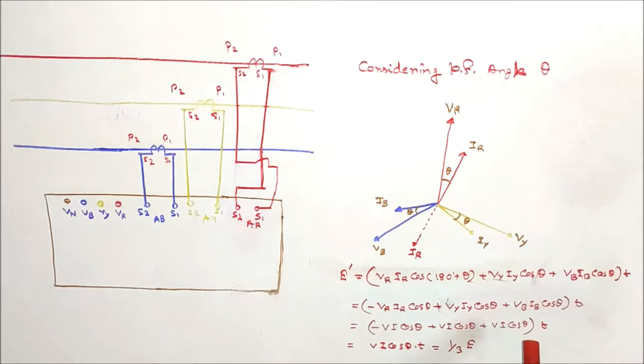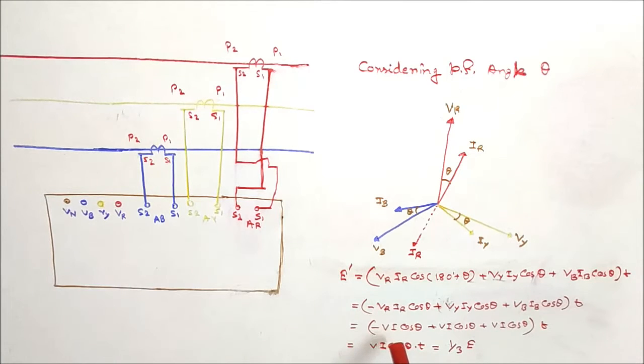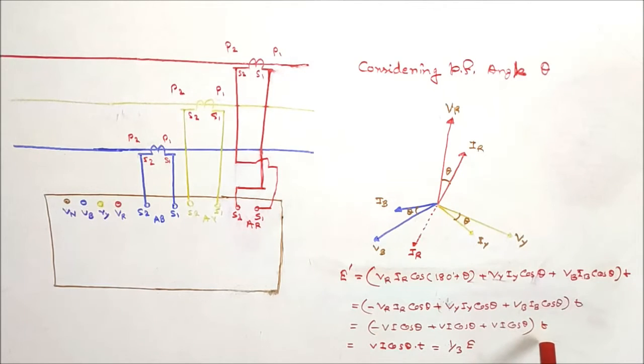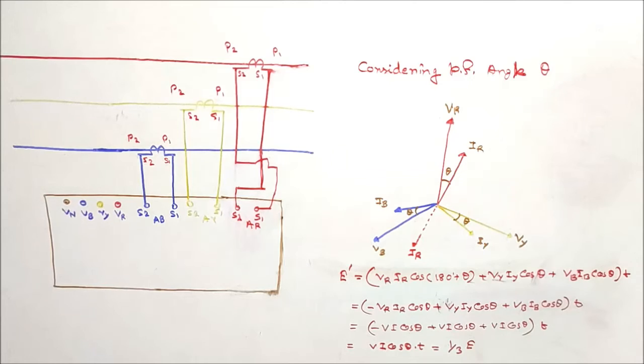Since it is a balanced three-phase supply, VR = VY = VB = V and all phase current magnitudes are equal to I. So red phase power = −V·I·cos(theta), yellow phase = +V·I·cos(theta), and blue phase = +V·I·cos(theta), times T. The total energy comes as V·I·cos(theta)·T, which equals one-third of the normal energy. So if any one CT polarity is wrongly reversed, the total energy meter reading will be one-third of the actual energy.